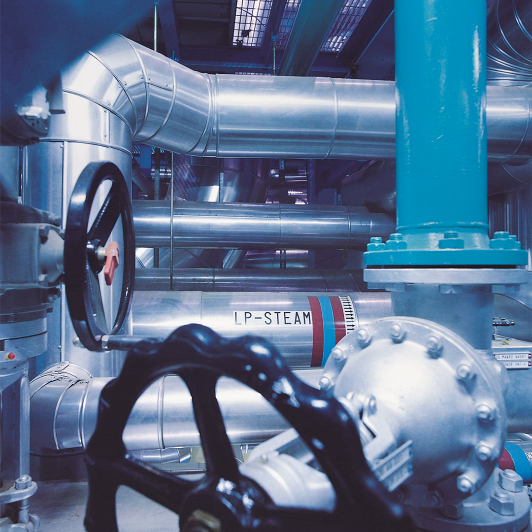But the normal or the standard control part is that we measure a temperature either in the supply line to the consumer, or we take temperatures from the consumers itself, from the rooms, and based on that decide where the valve should be positioned in order to adjust the capacity. Now, another line of thought would be, why don't we measure the flow that really goes into the consumer, that is provided by the supplier, and use that as part of the control strategy to make sure we get the right amount of capacity to the consumers.